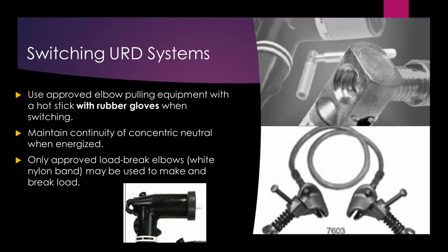When it gets into switching, like I just said about the elbow pulling equipment, maintain continuity on your concentric. Like I said about Eddie on the crew, he always smacked my hands if you didn't leave a drip loop or a little curly Q in that wire somewhere. Make sure you have enough on your concentric neutral that you can pull it off, move it, put it on a parking stand, something like that. If you just connect it straight to your 7-strand with a Kearney or split bolt, whatever you call it, whatever you use, make sure you have enough wire to be able to move that thing around.